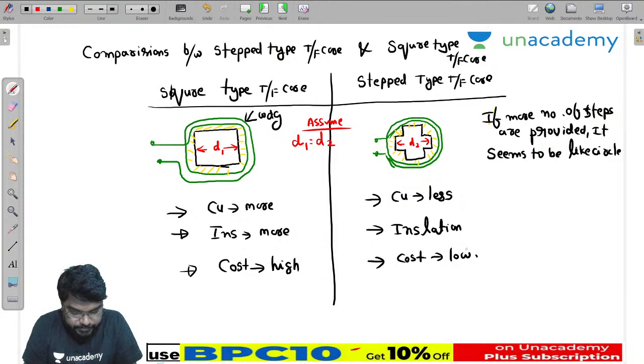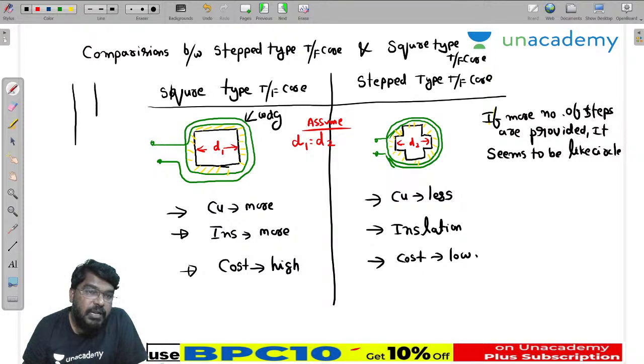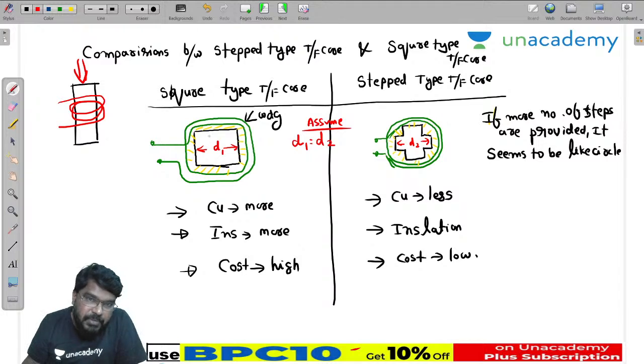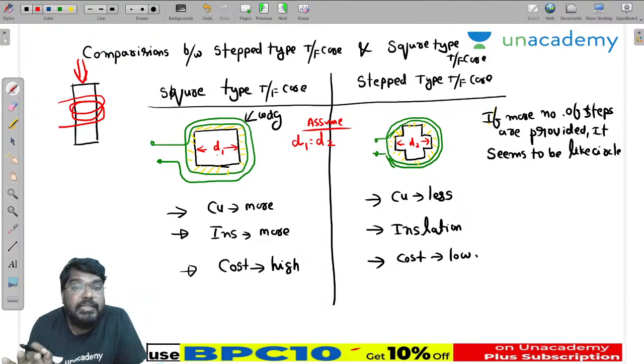So these are - actually this is one limb of the transformer, right? Winding is placed on the limbs like this. I have taken just a top view, so from the top view, winding is placed on the limb. The length of the copper wire per each turn on the limb is high in case of the square type, and the length of copper wire in case of the step type transformer core per each turn is small as compared to the square type transformer core.